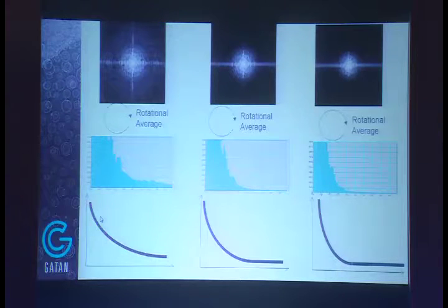So if you see a DQE curve that's relatively high here and falls off at the end, that's a better DQE curve than if you see one that falls off quickly and sort of goes along zero for the rest of the image. Okay, so rather than getting into the details of calculating DQE, that's how I think about DQE when I'm looking at it.